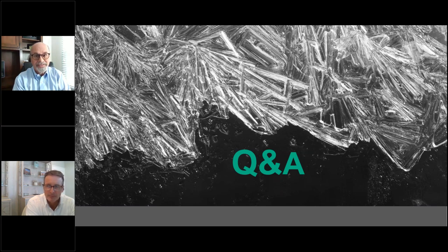Okay, and great. As Sylvain mentioned, any good validation technician will require you to go through a defrost cycle on that temperature mapping. They want to make sure that they're challenging the worst case scenario, and that's part of it.